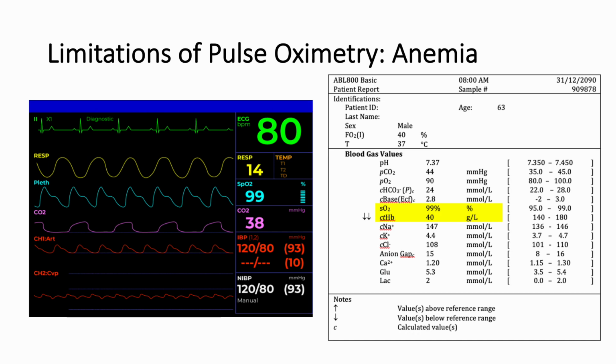It's important to realize that because pulse oximetry is only capable of detecting the oxygen saturations of hemoglobin, the reported oxygen saturation as determined by pulse oximetry for a severely anemic patient could easily report an oxygen saturation of 100%, which would technically be accurate. This is obviously problematic, as this high oxygen saturation value may provide a false sense of security regarding overall oxygen balance, as it does not provide any information about the fact that the patient is severely anemic and therefore may lack enough oxygen carrying capacity to keep up with the oxygen demand of vital organs.